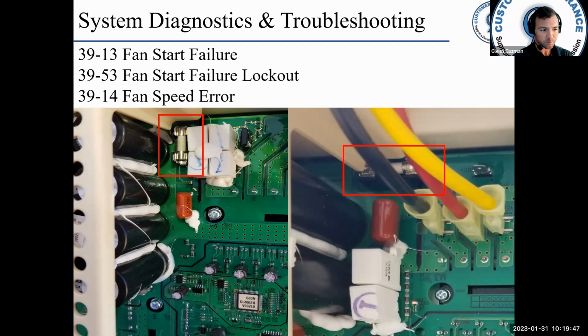the VFD. After 25 seconds, the FG wire, which is the fan speed signal feedback, if it equals 0, the PCM will reset the VFD and try to start again. After 3 VFD resets, code 3913 will be set and most likely accompanied by another fault, 8815 VFD reset.